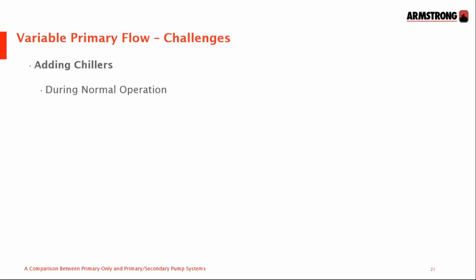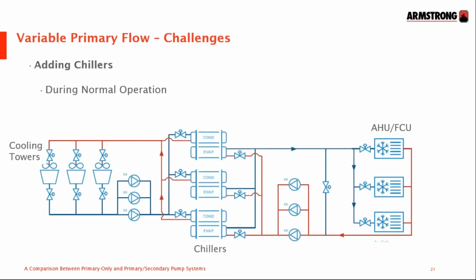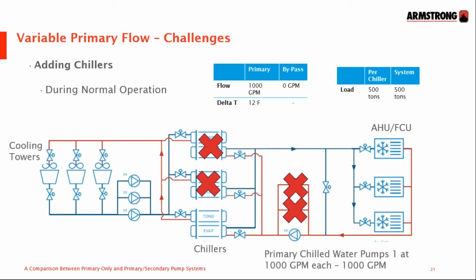So let's look at how this plays out in practice with regard to the rate of change and how the chillers are operated. Say during normal operation at low load we have just one chiller working, and the load is going up. The chilled water return temperature is getting higher than 56. This chiller is at maximum load, and we need to bring in another chiller in order to keep the chilled water supply temperature down at 44.